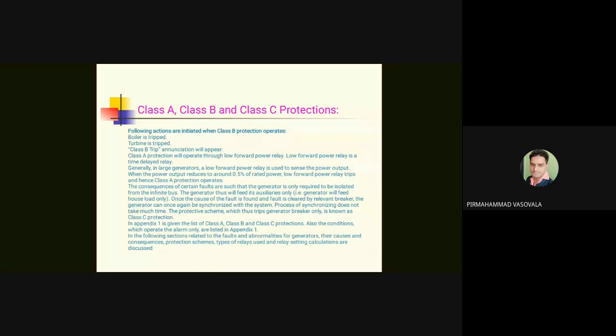Reverse means the power was being fed to the bus. Now, the bus will feed power to the generator. The generator will start motoring. At this juncture, the class A protection will operate, and class B, in a way, finally results in class A. But then we have made use of the kinetic energy of the generator, of the large inertia we have, and we have avoided the possible damage to the rotor parts of the generator.